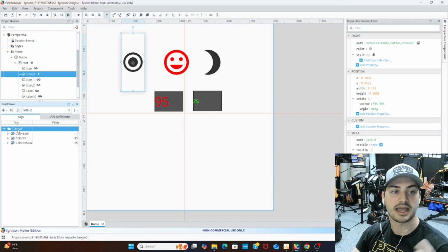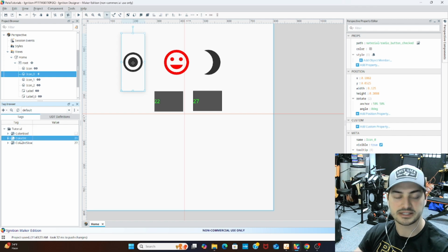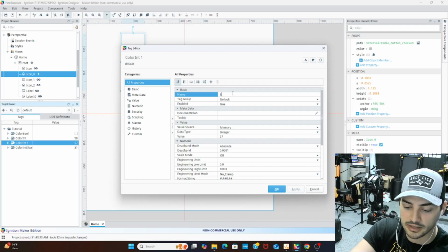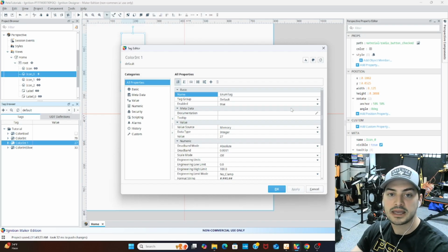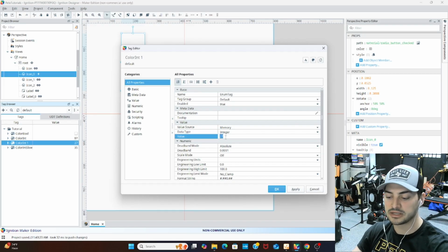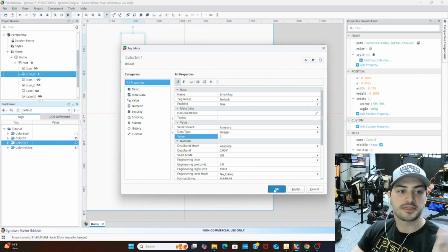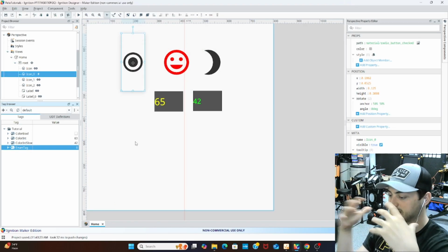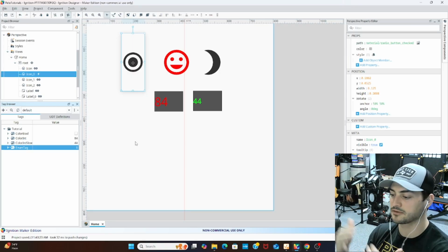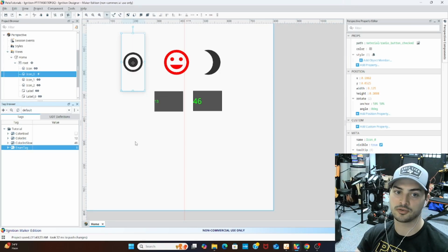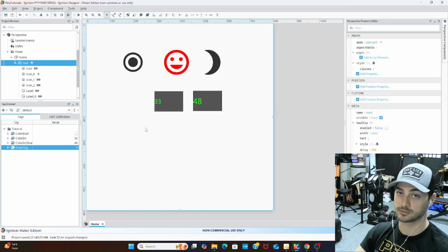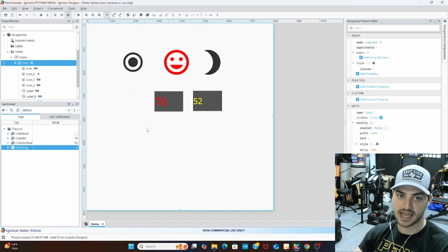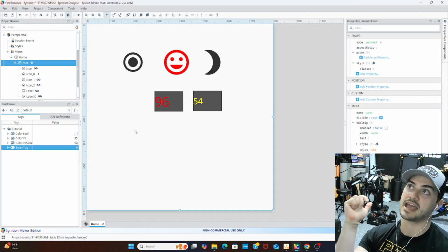integer. And I think this is super useful because it's kind of the basis of like enumeration, which is why I'm going to call it an enum tag. And it's going to be an integer, and I'm going to initially set it to 0. And the thing about enumeration is it's embedding detailed text status or some meaningful thing in an integer value, because PLCs don't always want to store long strings of text when they could just store it as an integer.